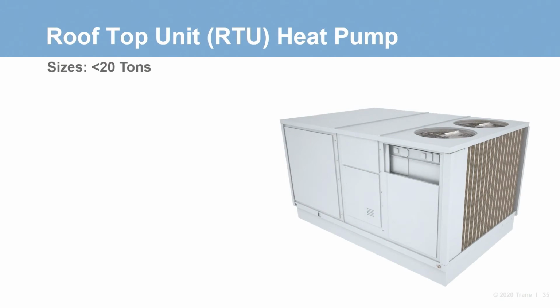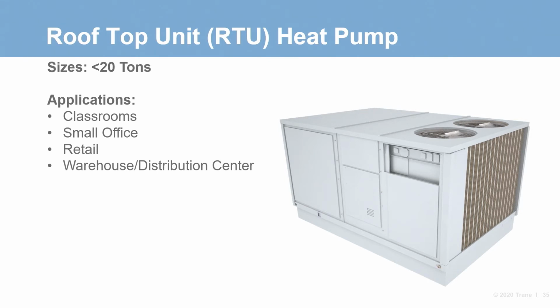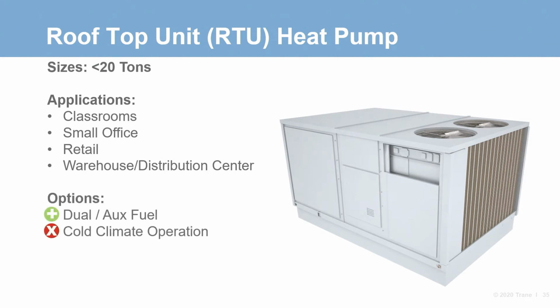All right, next we'll start to look at some packaged units. And first is rooftops. These are typically offered with heat pump capability 20 tons and under. Rooftop heat pumps are a great electrification package because the unit can handle all aspects of the system: heating, cooling, ventilation, and controls. Typical applications will be similar to current rooftop unit applications, so classrooms, warehouse, small office, and retail, just to name a few. A limiting factor for many RTU heat pumps is cold ambient operation.